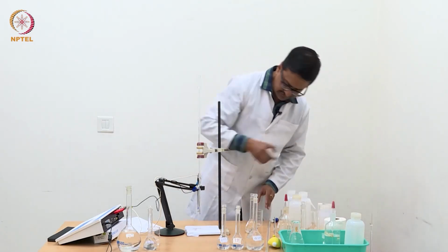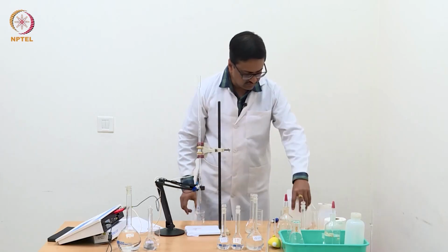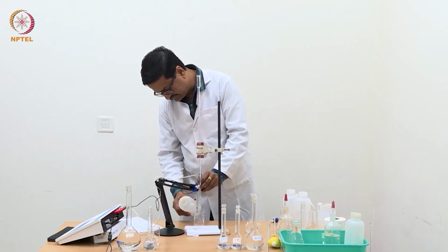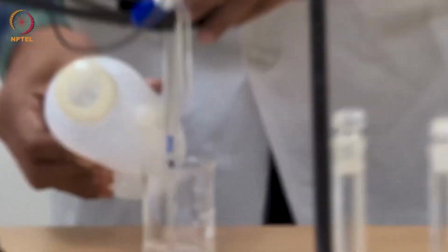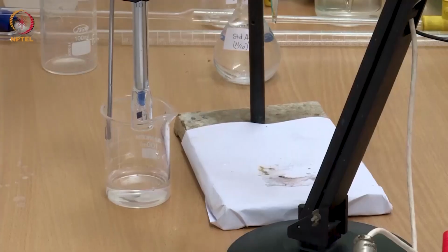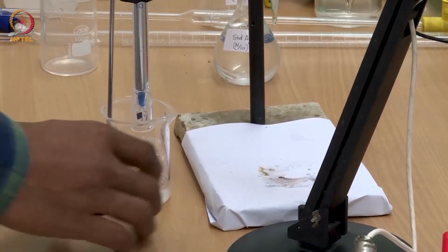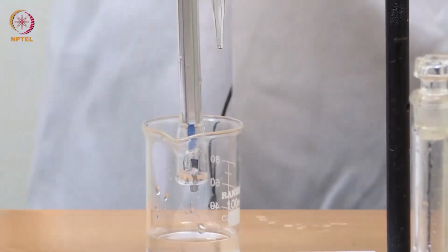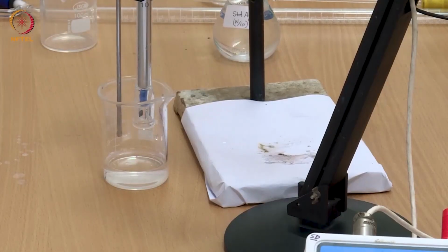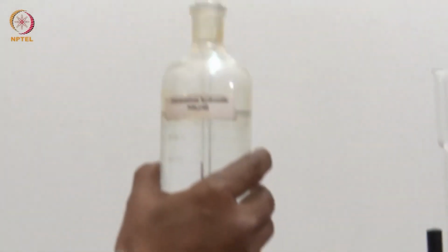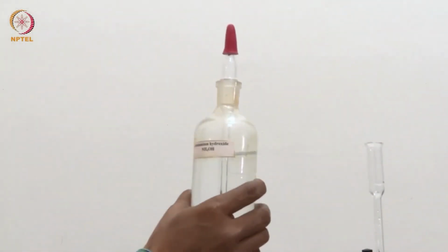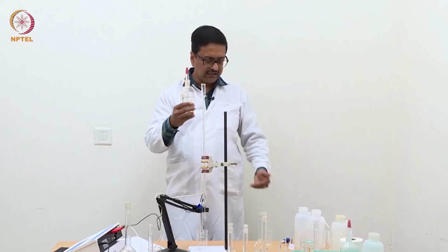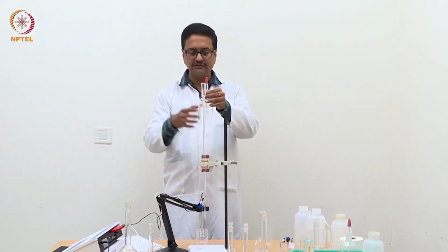We take a separate beaker first to quickly wash the electrode with distilled water, and you know that distilled water is not enough, it cannot dissolve silver chloride which may have got deposited on this electrode.